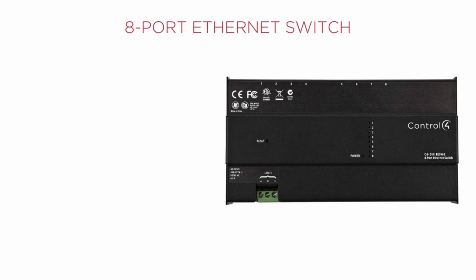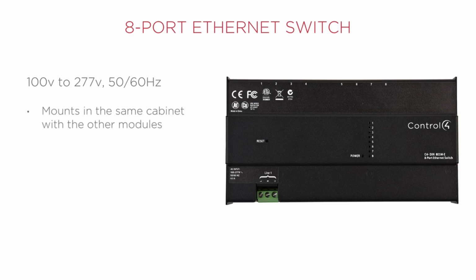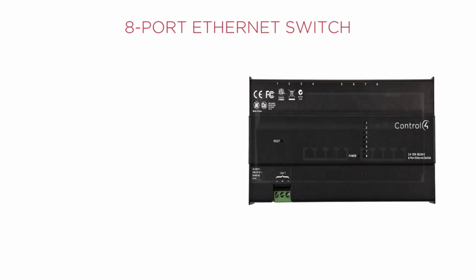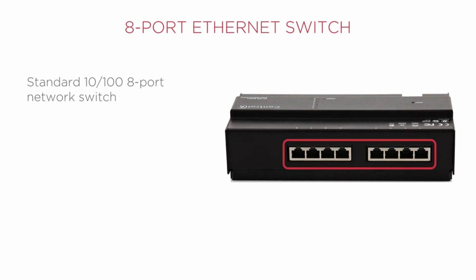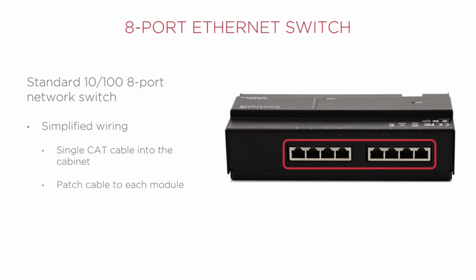The 8-port Ethernet switch. The 8-port Ethernet switch can run on 100 to 277 volts at 50 or 60 Hz and mounts in the same cabinet with the other modules. It also uses the same form factor to match the other modules. It features a standard 10-100 8-port Ethernet switch. It is not a gigabit switch, as the other Control4 centralized lighting modules do not require a gigabit connection. Using this Ethernet switch module simplifies the wiring, requires a single CAT cable to the cabinet, and a short patch cable from this to each of the other modules.